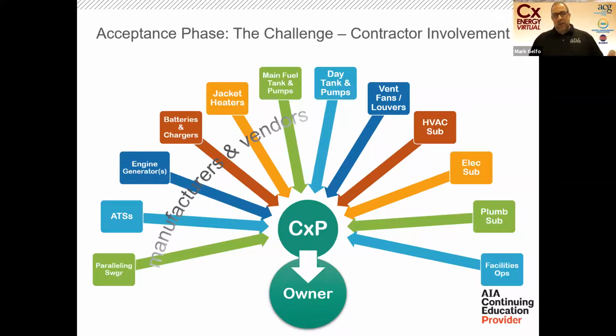I hear that so much when we're doing emergency power testing, because there are so many different pieces and parts and players involved, and we're like the conductor trying to get all these different players together. There's the general contractor, the electrical contractor, the generator provider, the switchgear and transfer switch vendors, the HVAC subs, and the fuel system, which is usually the plumbing contractor - a different vendor. So many people have to be involved throughout the process just to commission the emergency power system through construction, and certainly in the acceptance testing phase. That's one of our biggest challenges - getting all these people singing to the same sheet of music, if you will.